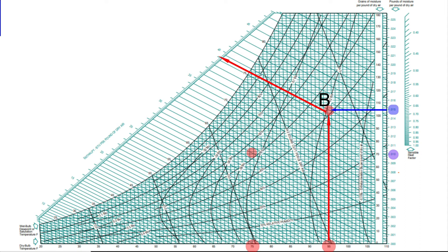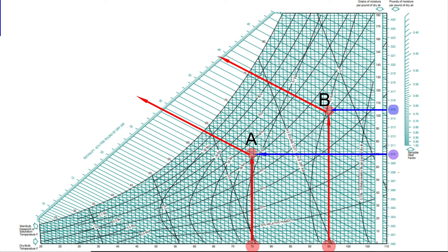The indoor dry bulb condition is 75°F with a wet bulb condition of 64.5°F. Using the same method on the psychrometric chart, draw a line from the dry bulb condition of 75°F to where it intersects the wet bulb condition of 64.5°F — call that point A. Then draw a line from point A to where it intersects the humidity ratio, which gives 0.010 pounds of moisture per pound of dry air. Now these values need to be converted from pounds of water to grains of water.